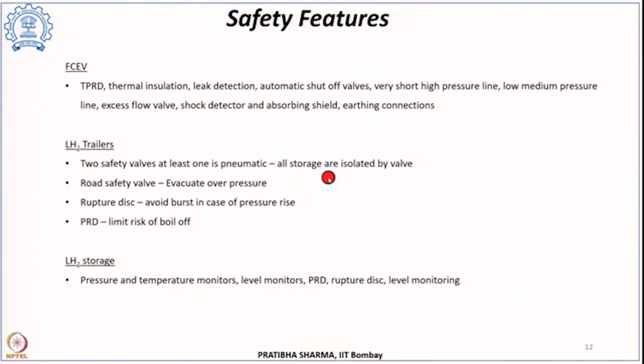With liquid hydrogen trailers, there are two safety valves provided, at least one of which is pneumatic, and all storage is isolated by means of valves. Besides that, there is a road safety valve to evacuate if there is any overpressure, and a rupture disc which bursts if there is a pressure rise in the trailer. There are also pressure relief devices so as to limit the risk of boil-off.